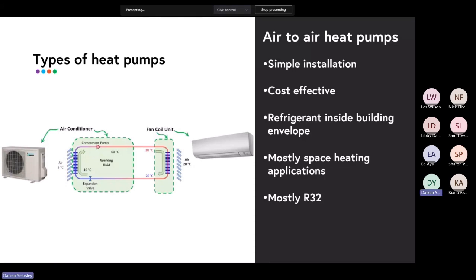So, just to clarify about bringing the refrigerant inside the building envelope, the reason why this is becoming more and more important is the newer refrigerants, what we call the natural refrigerants like R290, that is actually propane. So it is a flammable gas. It's classed A3, flammable gas. And so with these types of refrigerants, which are very, very good in terms of GWP, are not very flexible when it comes to actually piping it through the building.